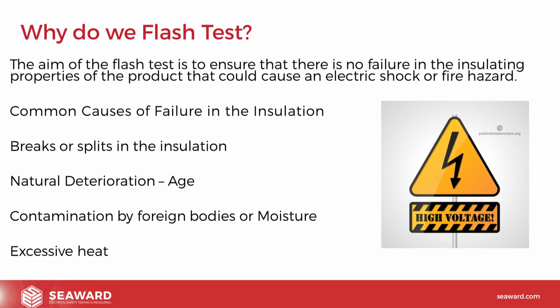Some of the common causes of failure in the insulation that we will pick up when performing the test: any kind of breaks or splits in the insulation. When we talk about breaks or splits in the insulation, what we're talking about is potentially somewhere where the live conductors can conduct to either the outer casing or to any of the earth cabling and therefore present a shock hazard. Over time, with use, particularly with products that are left out in the cold, you'll get some deterioration. The cables will become brittle. Again, they'll be susceptible to crack or break.